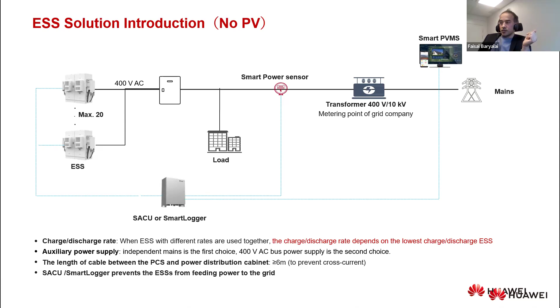We also have scenarios with non-compatible inverters where we use 2 transformers. Practically, this kind of system is also allowed. We have 2 transformers, one on the PV side, one on the ESS side, and the configuration could be either solution 1 or solution 2. But in this case, we need 1 extra smart logger.